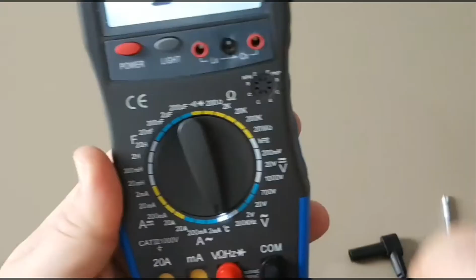Okay, so probably not entirely fair, but I've got a Fluke 87V and it's in temperature mode, and we're going to compare the two. Right now the HOLDPEAK is showing us around 26 degrees as the ambient temperature, in Celsius. The Fluke is showing us about 22.9. So about a 3 degree offset.